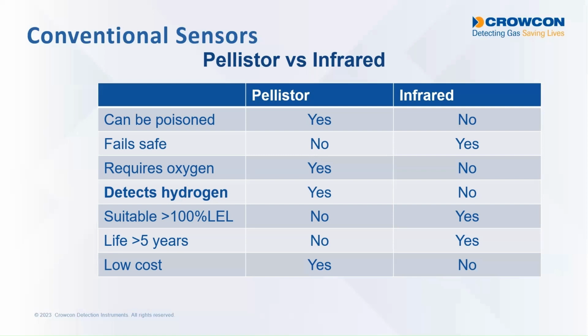And being a thermal device, a pellistor has a relatively limited life, 3 to 5 years in most applications, but then the pellistor has to be replaced, whereas an infrared detector will last 10, 15 years plus. And a pellistor is a fairly low cost device, whereas an infrared detector, being more sophisticated, is a slightly more expensive device.